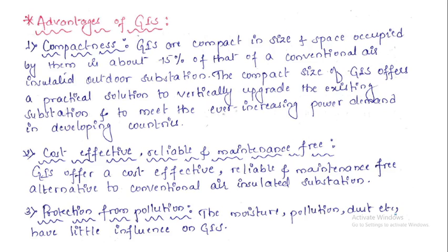The first point is compactness. GIS are compact in size and the space required by them is about 15% of that of a conventional air insulated outdoor substation. As I have already mentioned, the size is going to be reduced. The compact size of GIS offers a practical solution to vertically upgrade the existing substations and to meet the ever increasing power demand in developing countries. As we know, in developing countries abundant space is not available. So within a permissible small space, we need to construct the substation within buildings. So these GIS are compact, and within the building we can have such GIS modules.